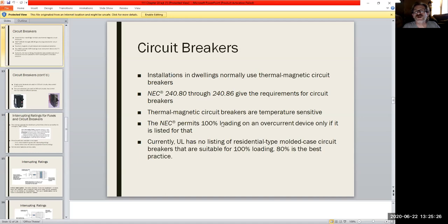But the NEC will permit 100% loading on an overcurrent device only if it is listed for that. What do they mean by that? Well, typically in a house, we don't usually load a line up 100%. Typically, your best practice is about 80% load, because you never really want to quite hit that threshold. So let's say you have a 20 amp line within your house, and you have enough devices in, say, a workshop that you're constantly pulling near the 20 amp margin on a very regular basis. Remember, this is never going to be a dead line. It's always going to fluctuate. So depending on what you're doing, over a certain amount of time, it would trip.